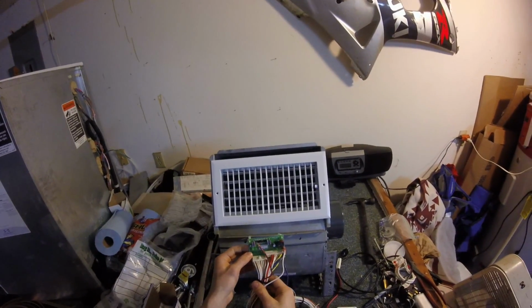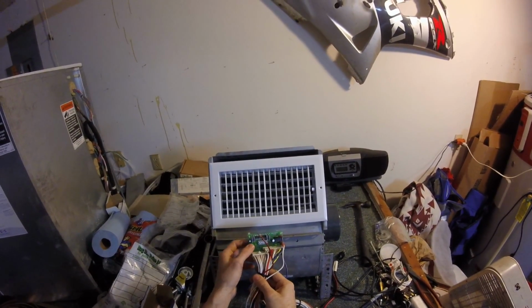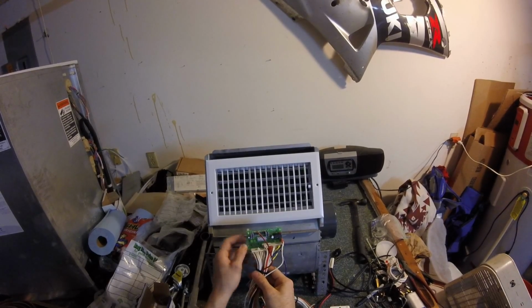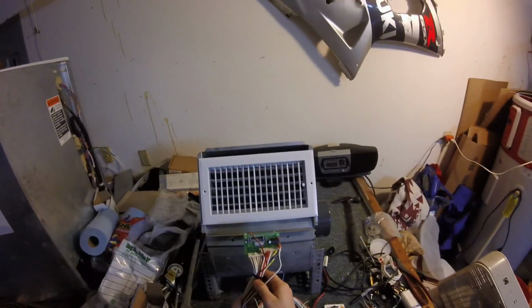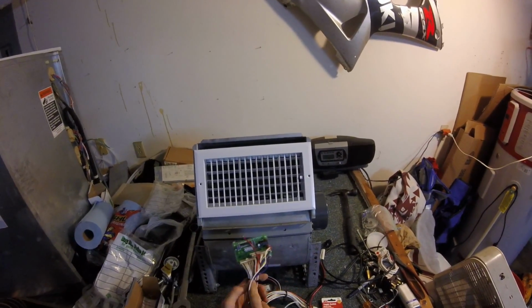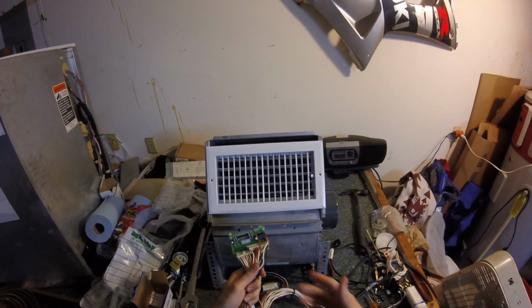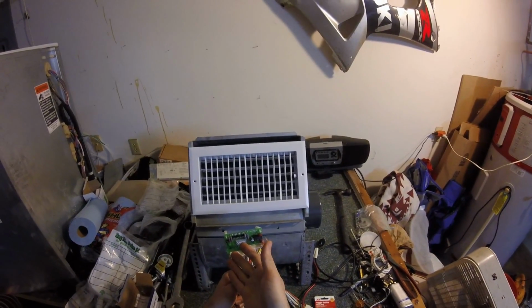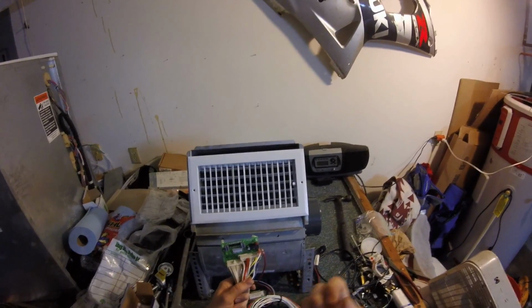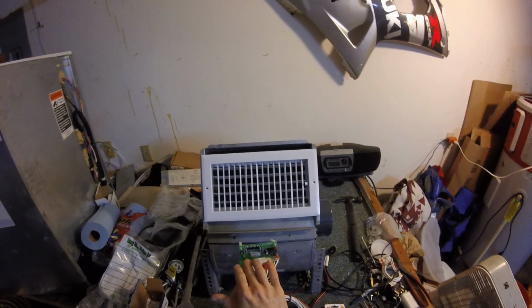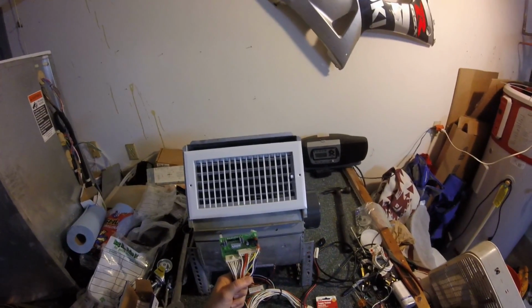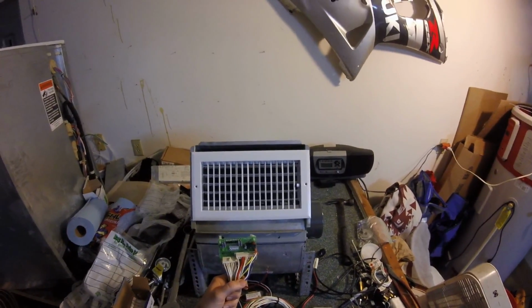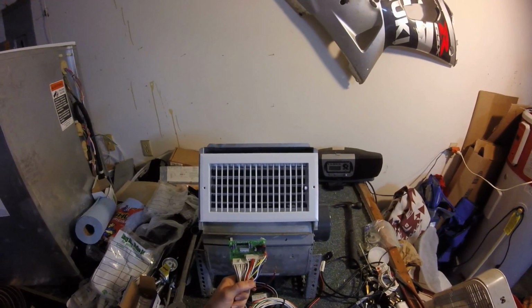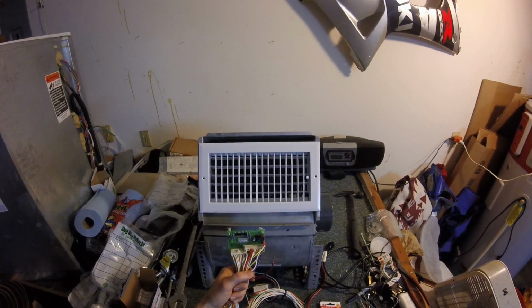I like these control boards because they have a CFM indicator light, whereas with others you're kind of guessing. You can also use this kind of board as a test or setup board, so you can count your CFMs, see what the motor's doing, and then switch it to a board that doesn't have a light, and still know what it's doing.